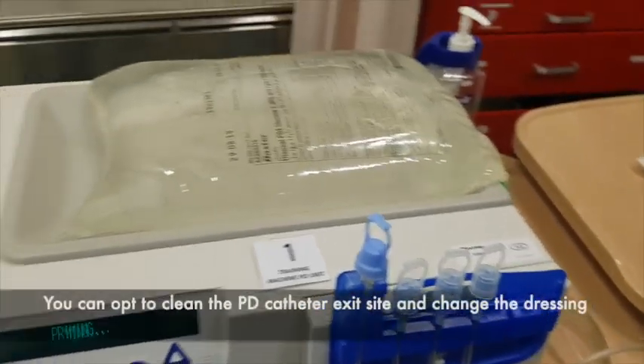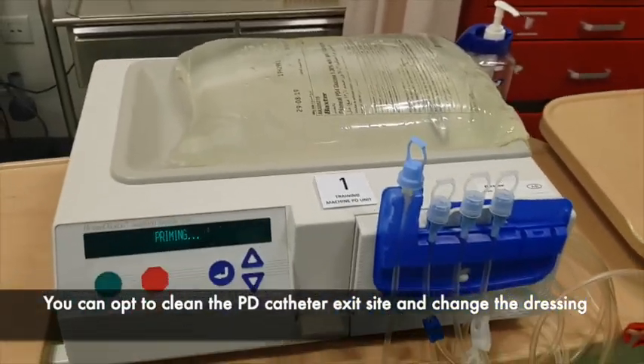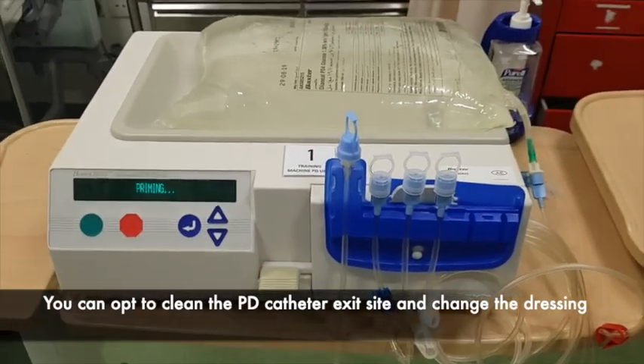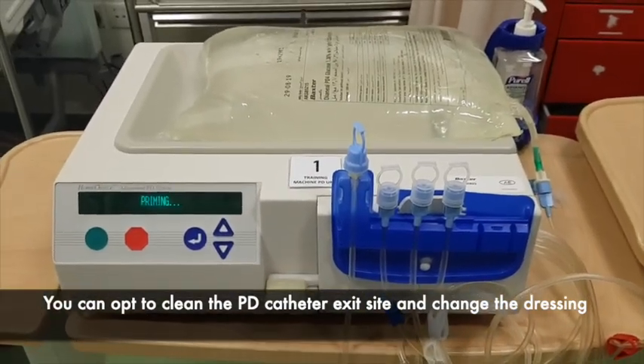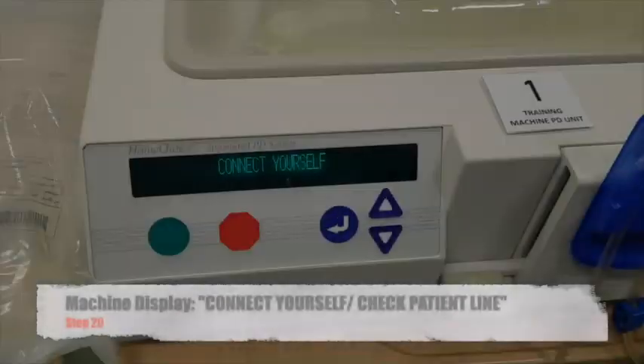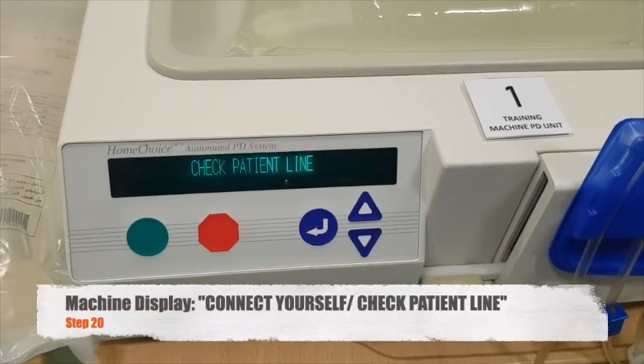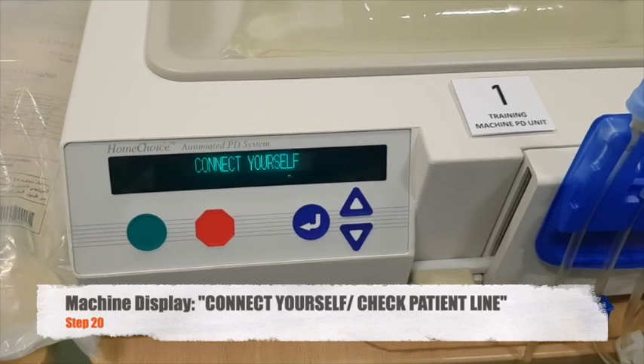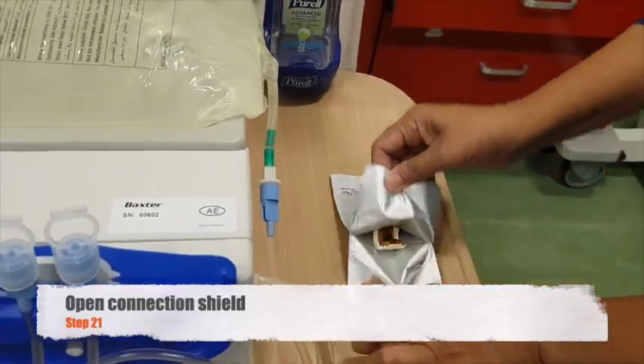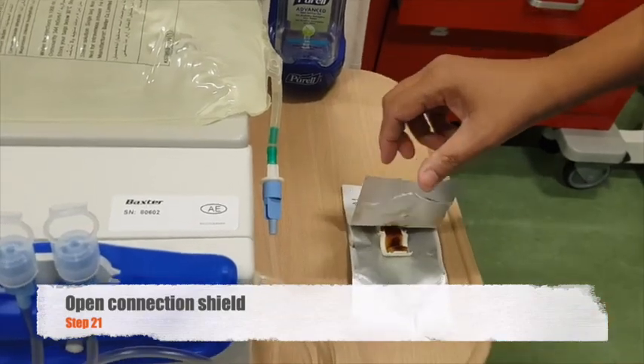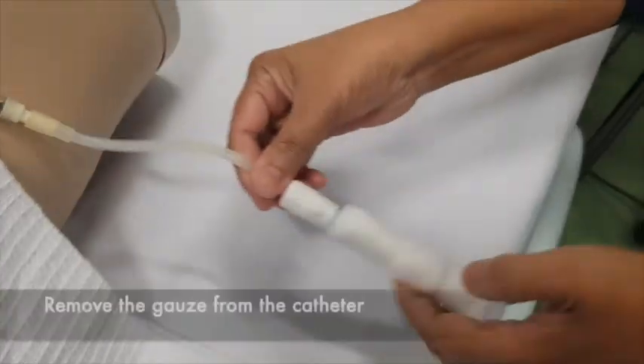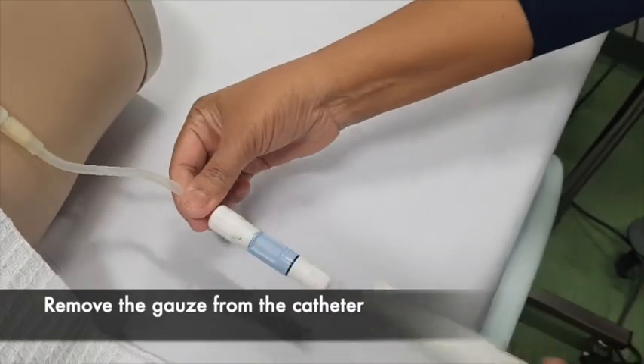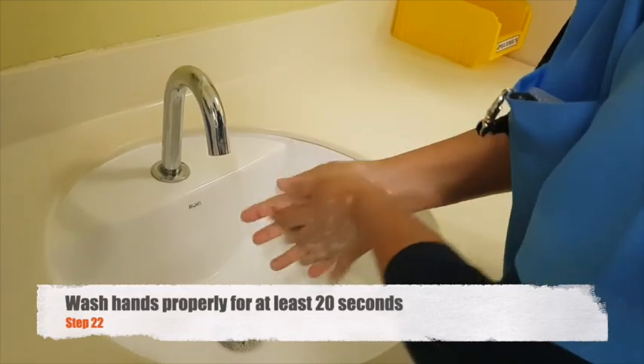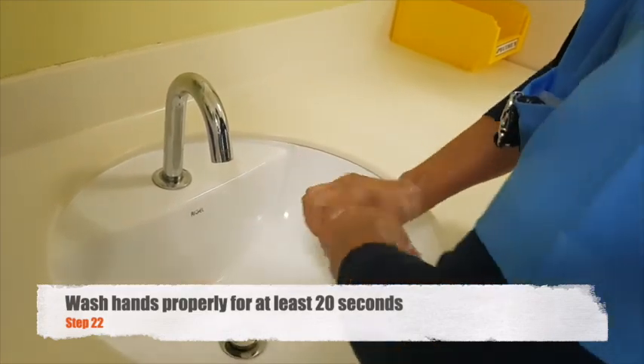At this point, while waiting for the machine to finish priming, you can opt to clean the PD catheter exit site and change the dressing. After finishing the priming, the machine will display Connect Yourself or Check the Patient Line. Open the connection shield and remove the gauze from the catheter. You can then wash your hands again for at least 20 seconds.